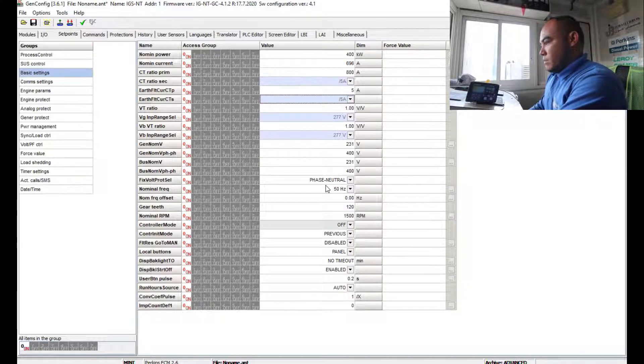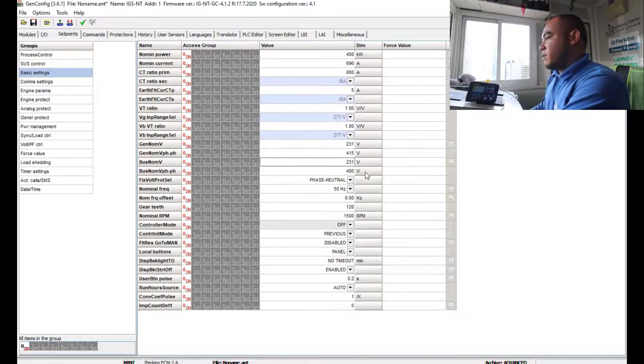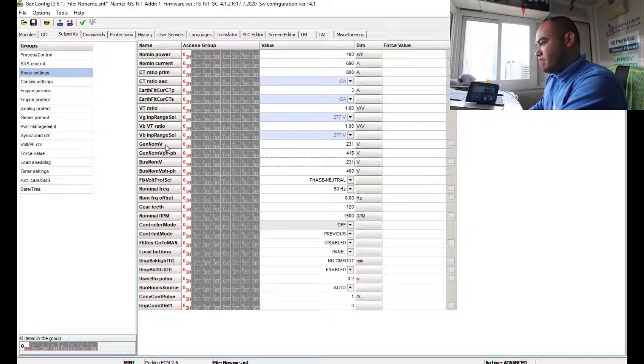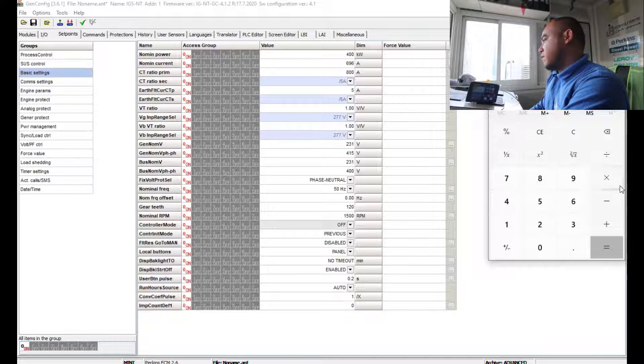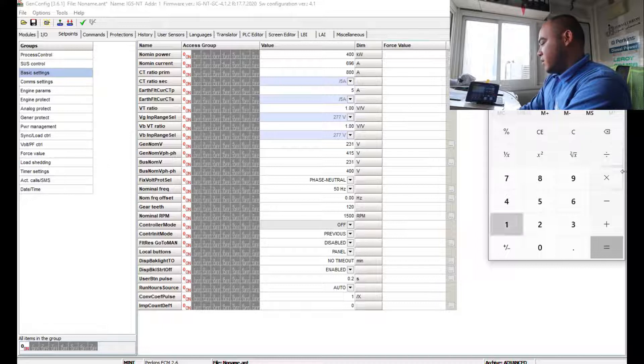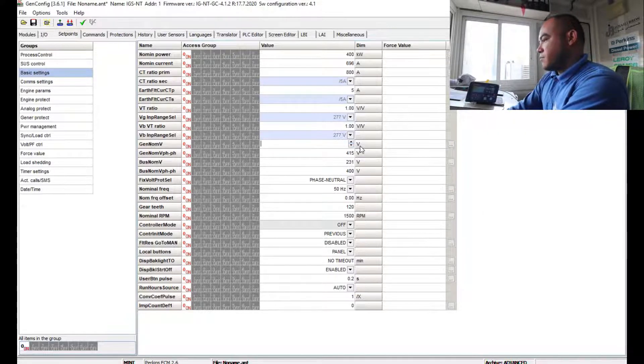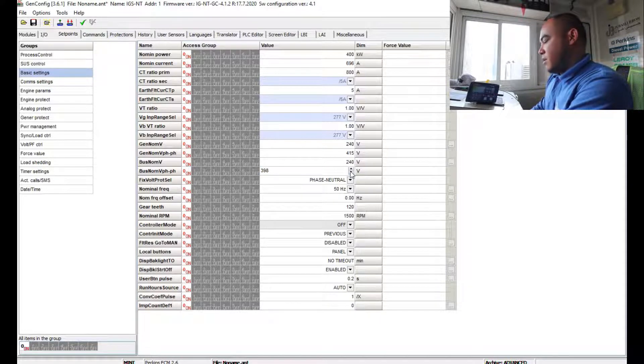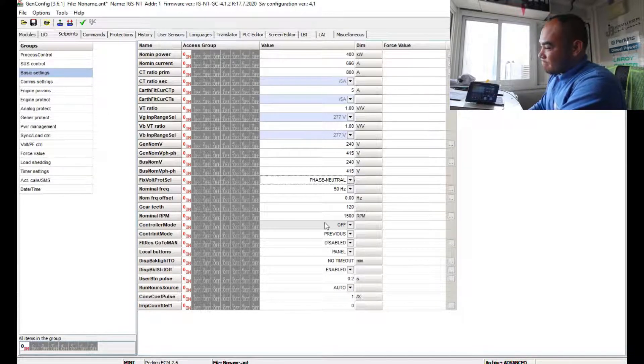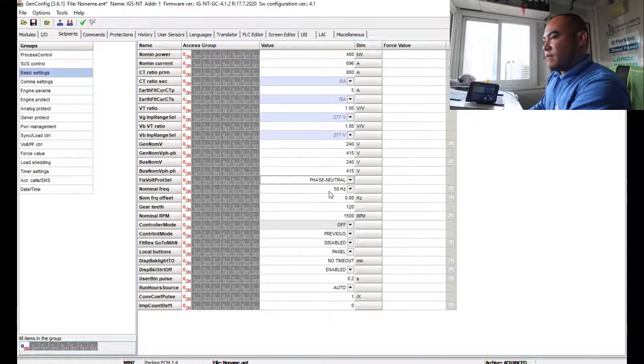For voltage settings, no need to change the default 400/300/400 references. If you are using 415V, enter 415 as the genset nominal voltage. To calculate the phase-to-neutral voltage, divide 415 by 1.732, which gives approximately 239–240V — enter 240V here and also in the field below. Since we are using 50 Hz, set frequency to 50 Hz.